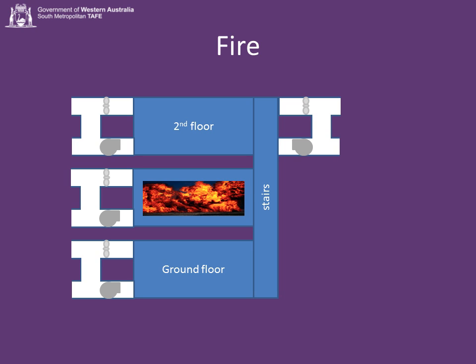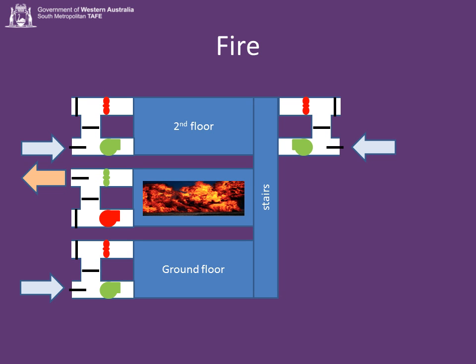What we can do in a fire, which is even better, is we can do what's called sandwich pressurization. With sandwich pressurization, we basically pressurize the surroundings of the fire. So we switch off the supply air fan to that fire, and we switch the return air fan on full so that we're sucking out from the fire. Where the fire actually is, we've got suction, so we're sucking out.